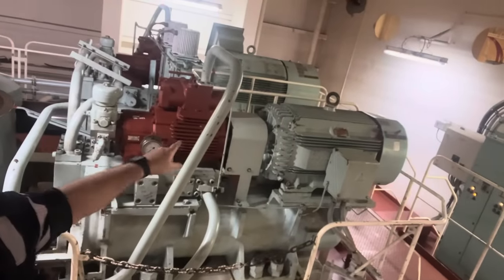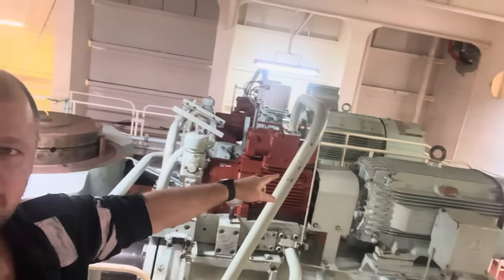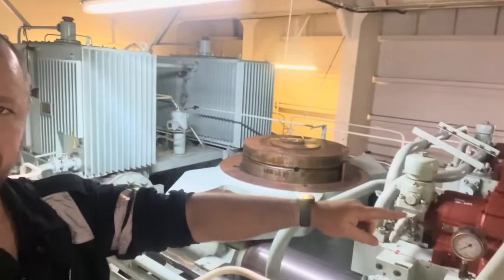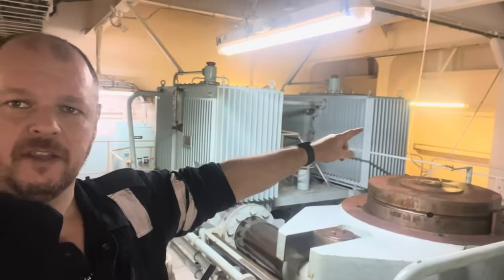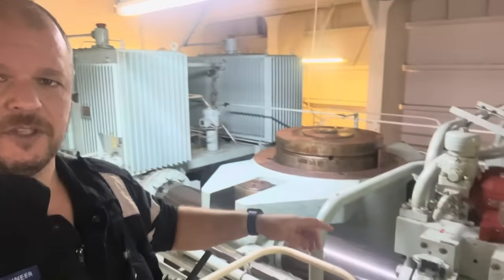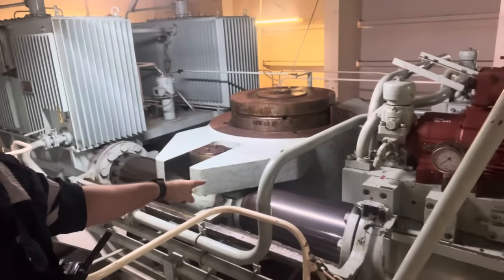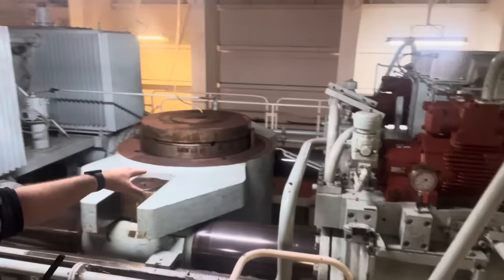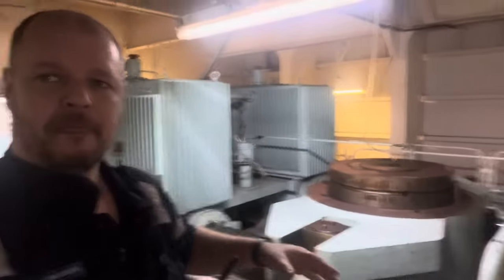I'll show you why they lost power and why they lost steering. What I've got here are two electric motors — completely separate and independent — that go to two different pumps. This is my rudder horn here, and I've got oil storage tanks back there with low-level alarms. There are a number of alarms on the system in general. You can see these giant hydraulic rams — there are four rams into this giant block — and this is an incredibly redundant system.